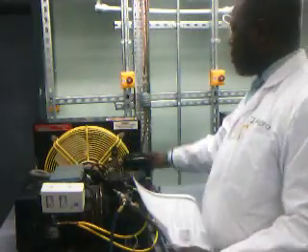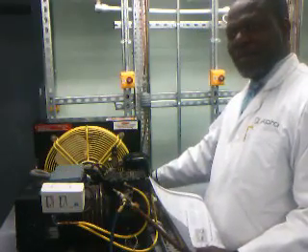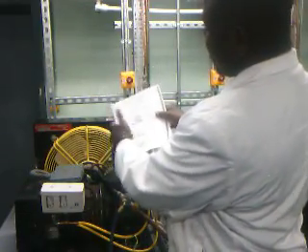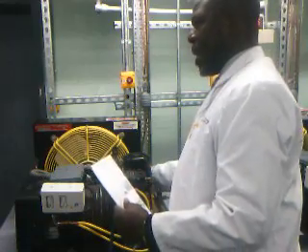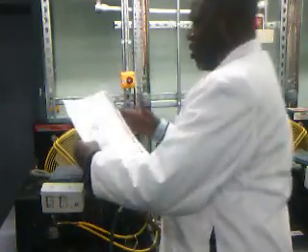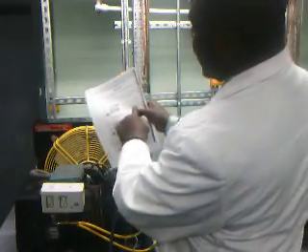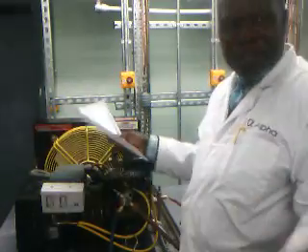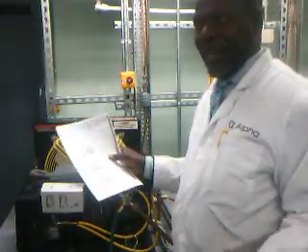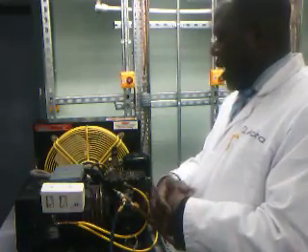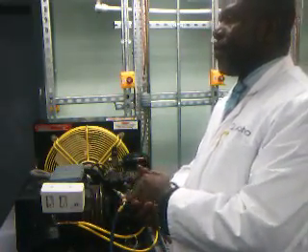And then you stick your thermometer on the outlet pipe and get a temperature from there using your probe. In this example, we have 34 on the pipe outlet, and then we have 39 towards the end of the condenser. So you do the subtraction, 39 minus 34, and then we get what? 5. So 5 degrees of subcooling is normal. That is all. That is normal. So anything above it is a problem.